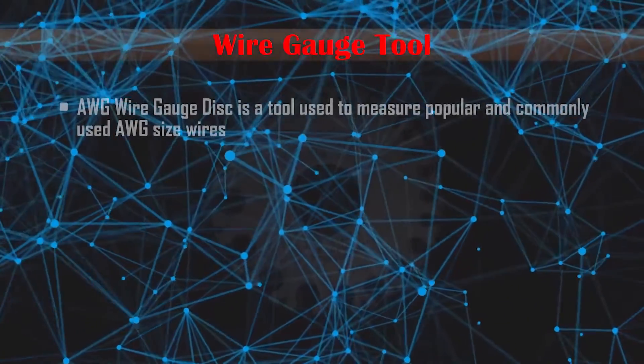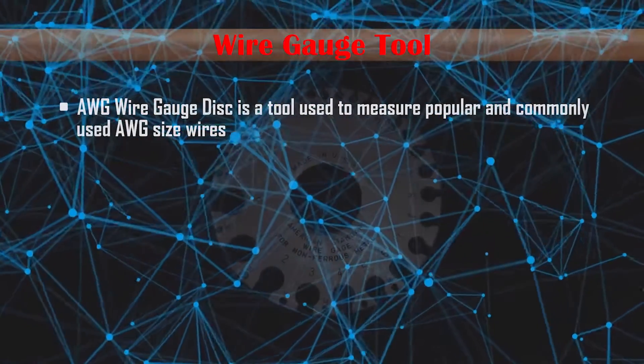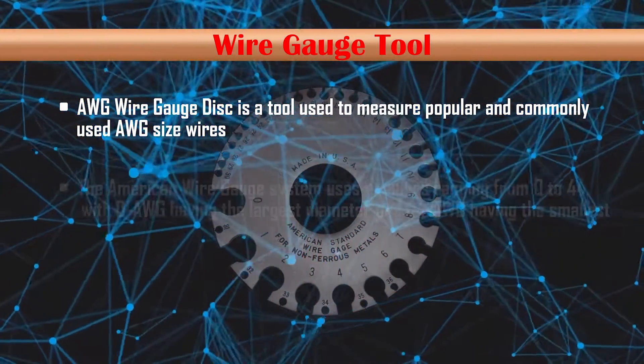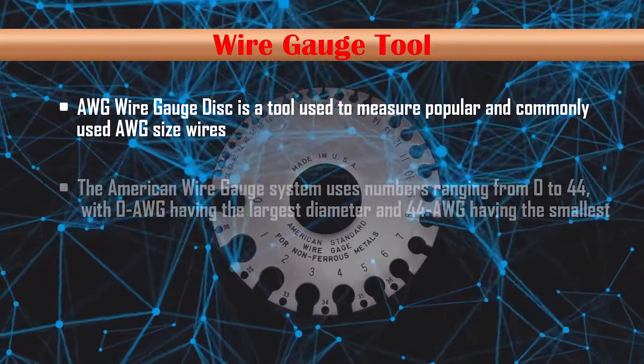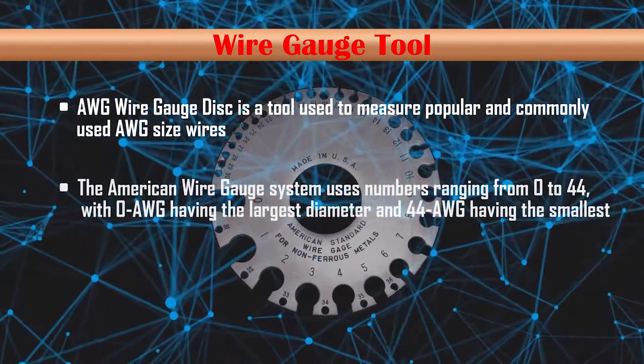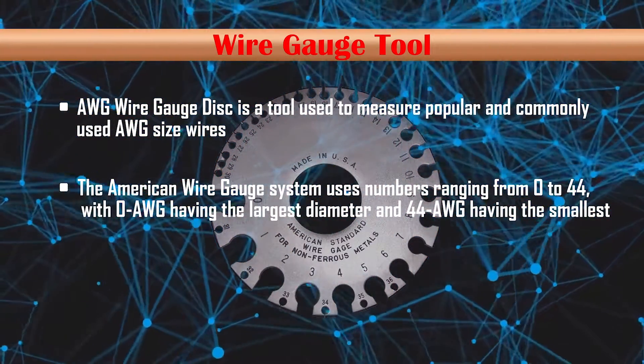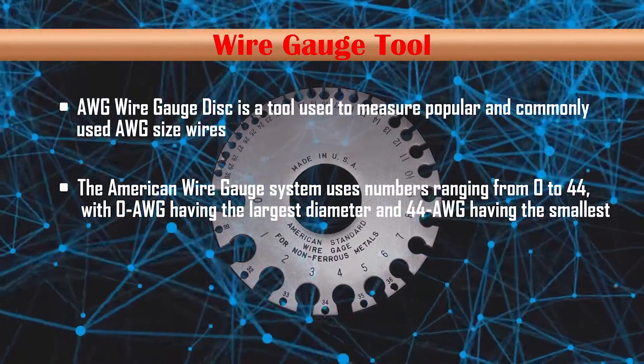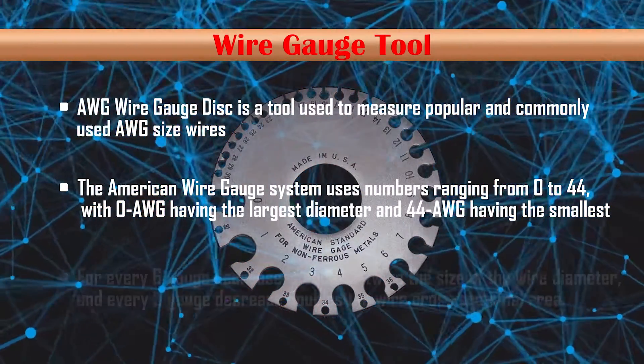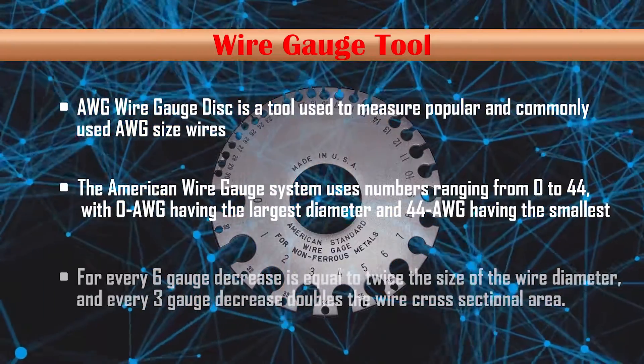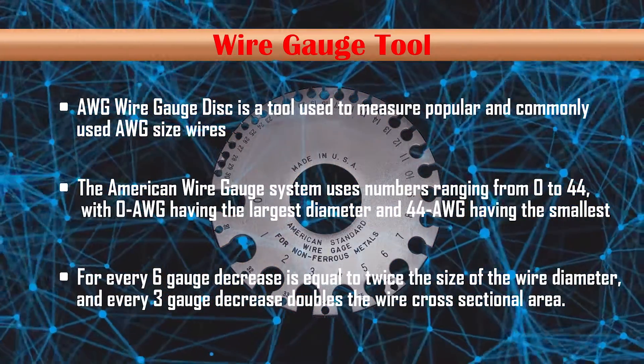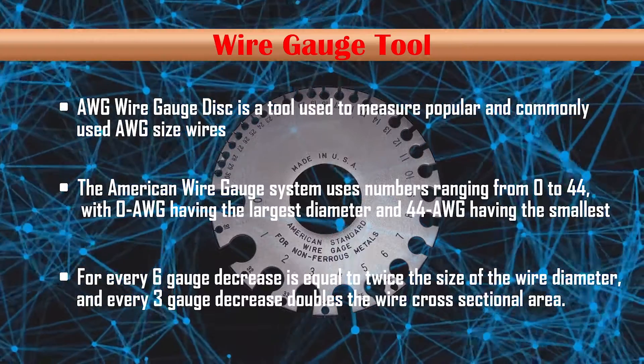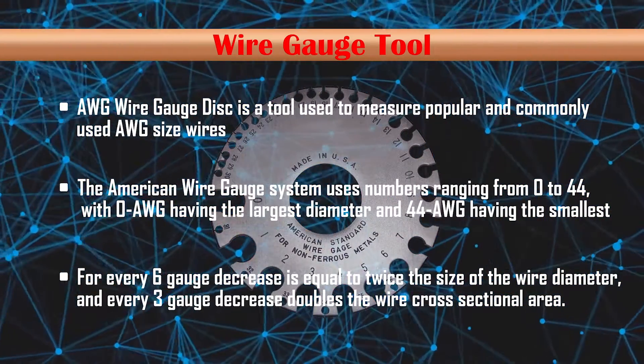An AWG wire gauge disc is a tool used to measure popular and commonly used AWG size wires. The American Wire Gauge system uses numbers ranging from 0 to 44, with 0 AWG having the largest diameter and 44 AWG having the smallest. For every six gauge decrease, the wire diameter doubles, and every three gauge decrease doubles the wire cross-sectional area.